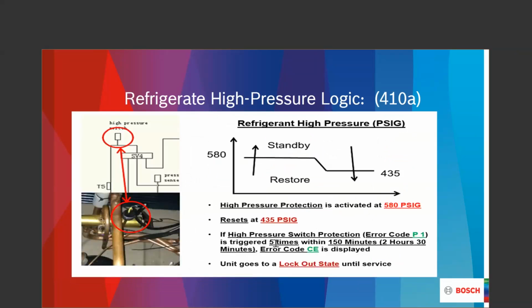When I'm looking at head pressure on the system, I can look at my 410A. When my head pressure, for some reason, gets over 580 PSIG, my system is going to protect itself and shut down. It is going to reset automatically when the pressure drops below the 435 range, and at that point in time there is an error code, C-E, that is going to be illuminated on the fault table and also illuminated on the LED screen.